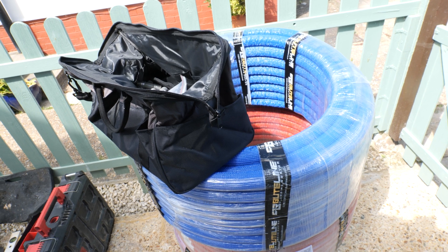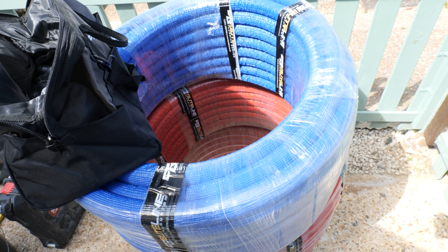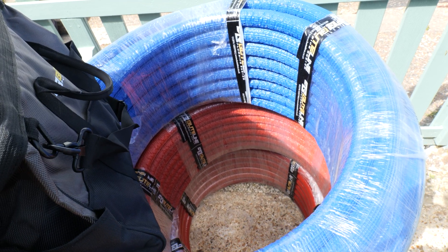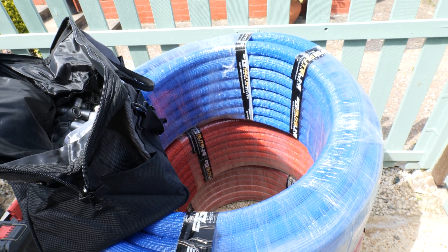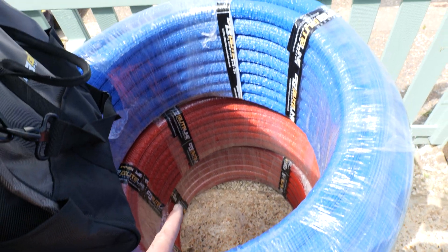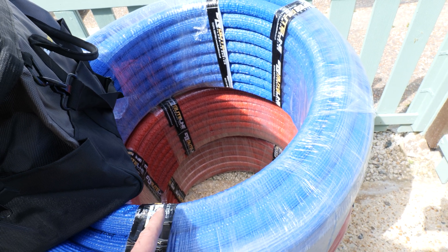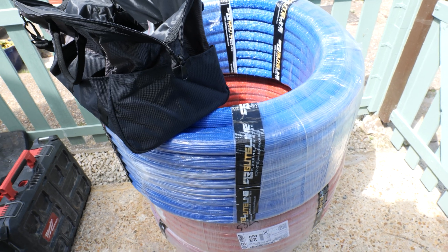On this occasion we've gone for the pre-insulated type, mainly because we need to conform with our building regulations. They do this in 22mm, 15mm and 10mm pre-insulated. As you can see, they also do it in colour coded - so in this job we're using blue for the cold and then flow, return and hot distribution in the red. Let's get this unrolled and start threading it through the ground floor joist space.